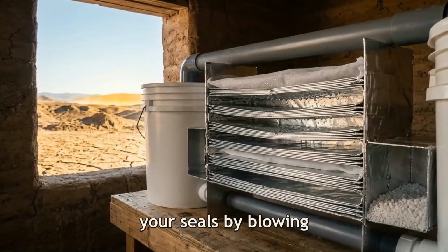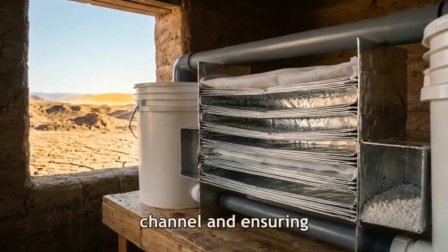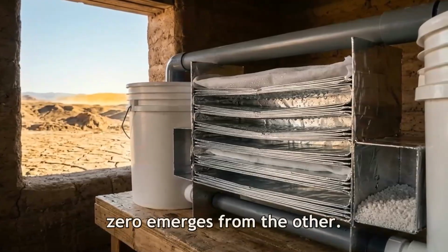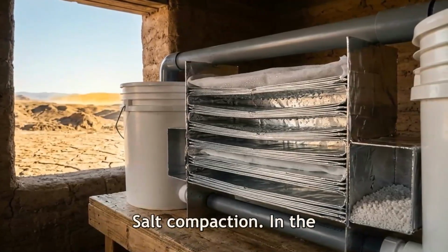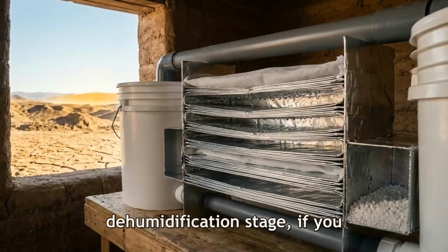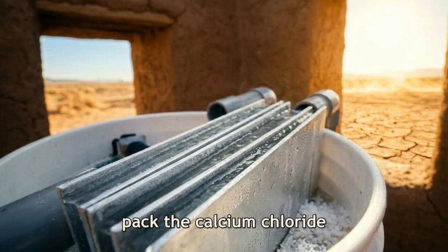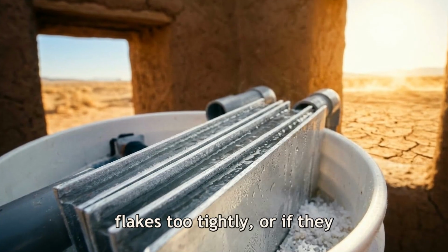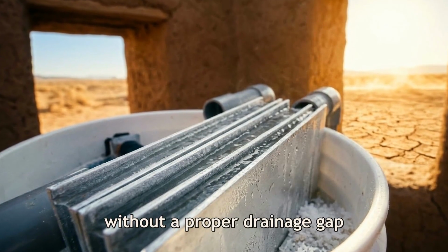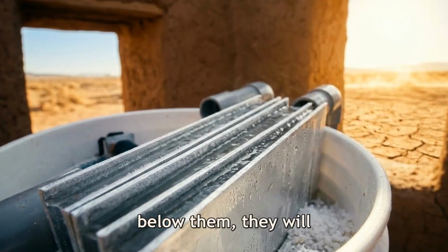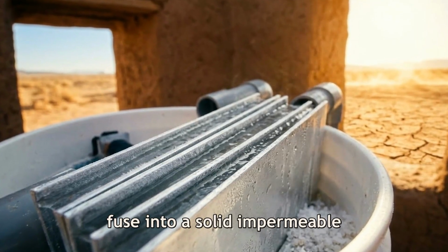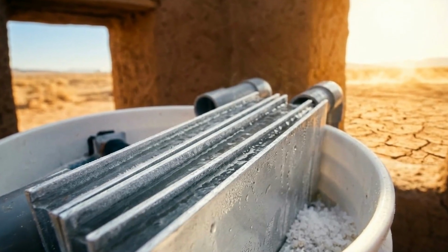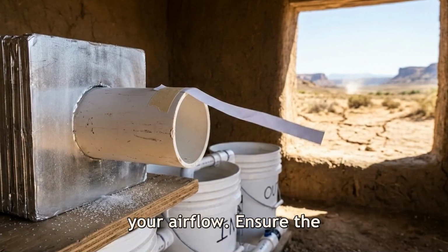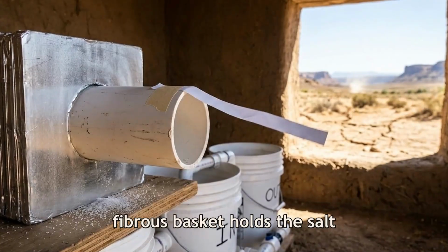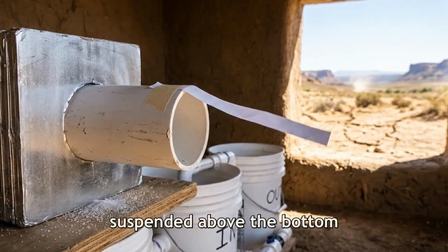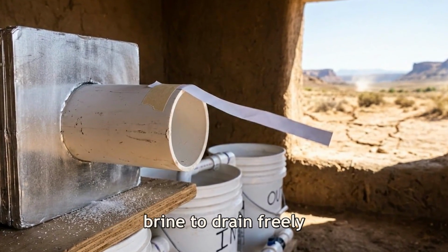Test your seals by blowing smoke or vapor through one channel and ensuring absolutely zero emerges from the other. Salt compaction. In the dehumidification stage, if you pack the calcium chloride flakes too tightly, or if they get completely soaked without a proper drainage gap below them, they will fuse into a solid, impermeable block of salt concrete. This will completely choke your airflow.